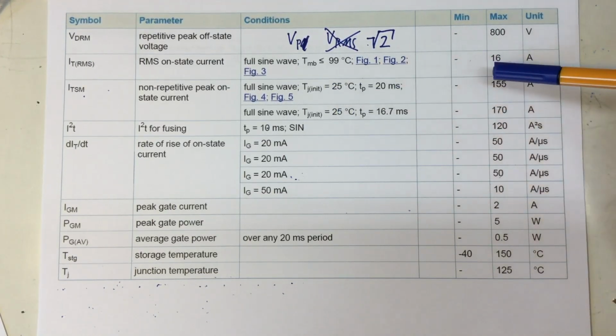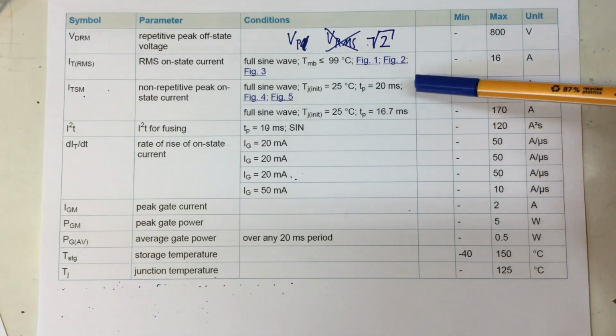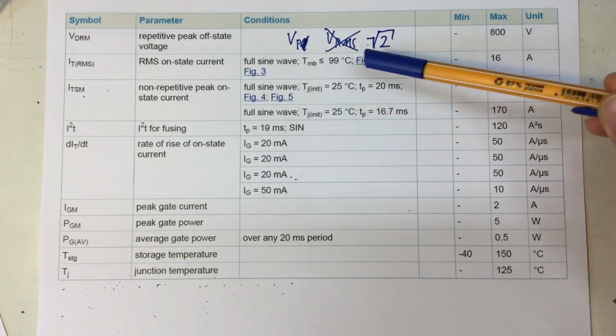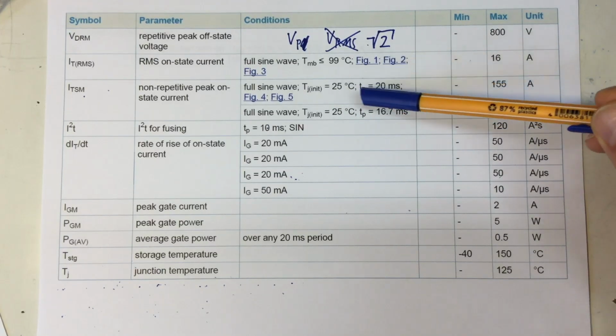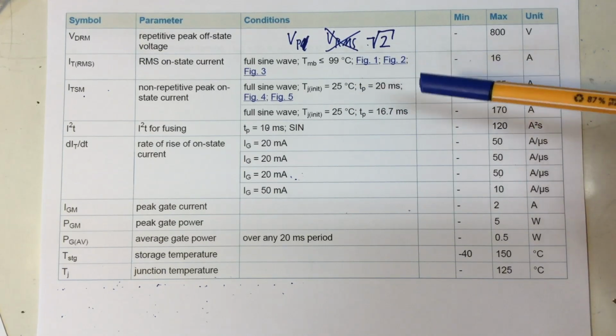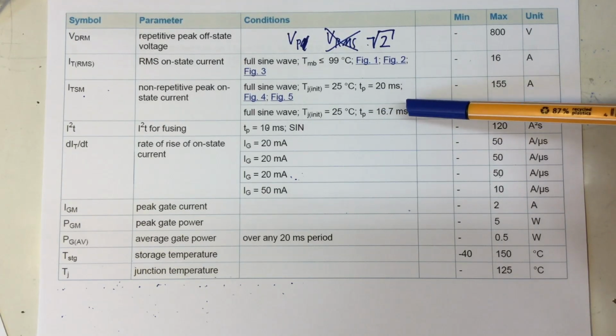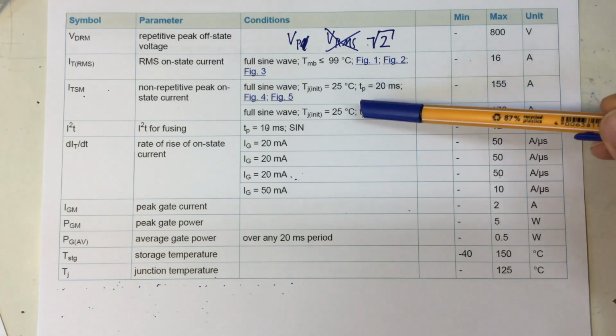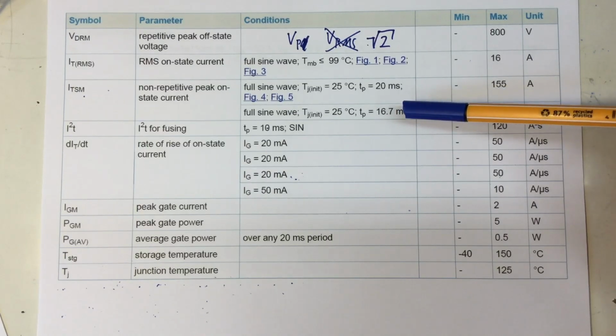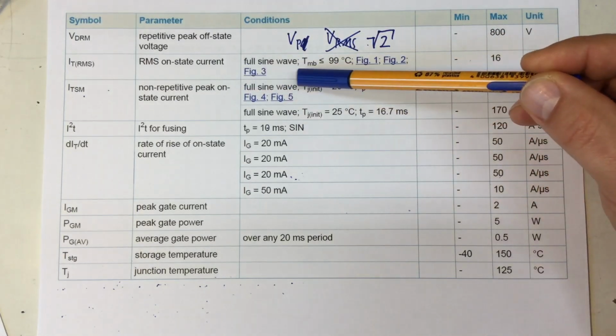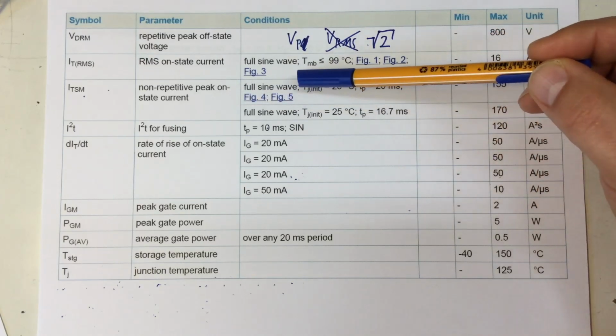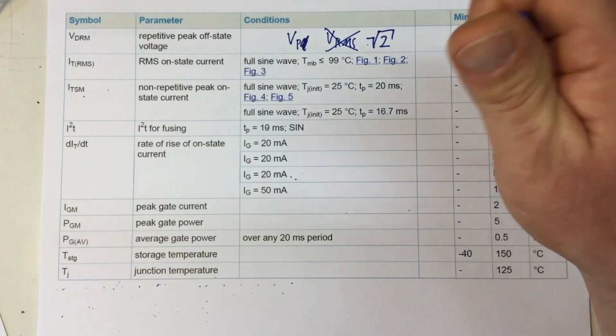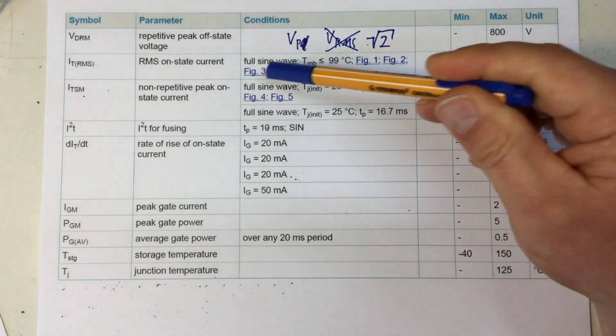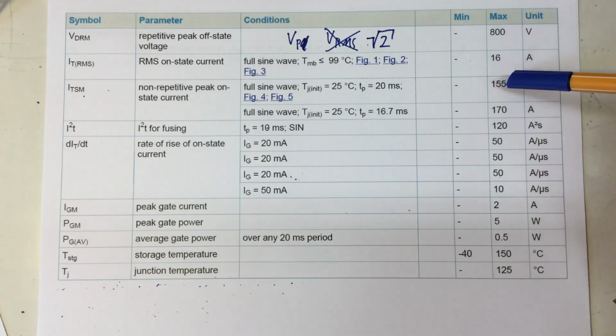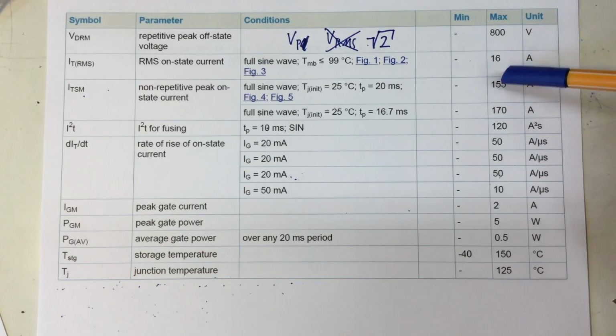And there are two values given here, one for 20 milliseconds, that's incidentally for 50 Hertz, if you think about it, and for 16.7 milliseconds, that's incidentally for 60 Hertz sine waves. And that peak is a full sine wave, I mean 1 full sine wave. Only one cycle passed through the device with that current here.